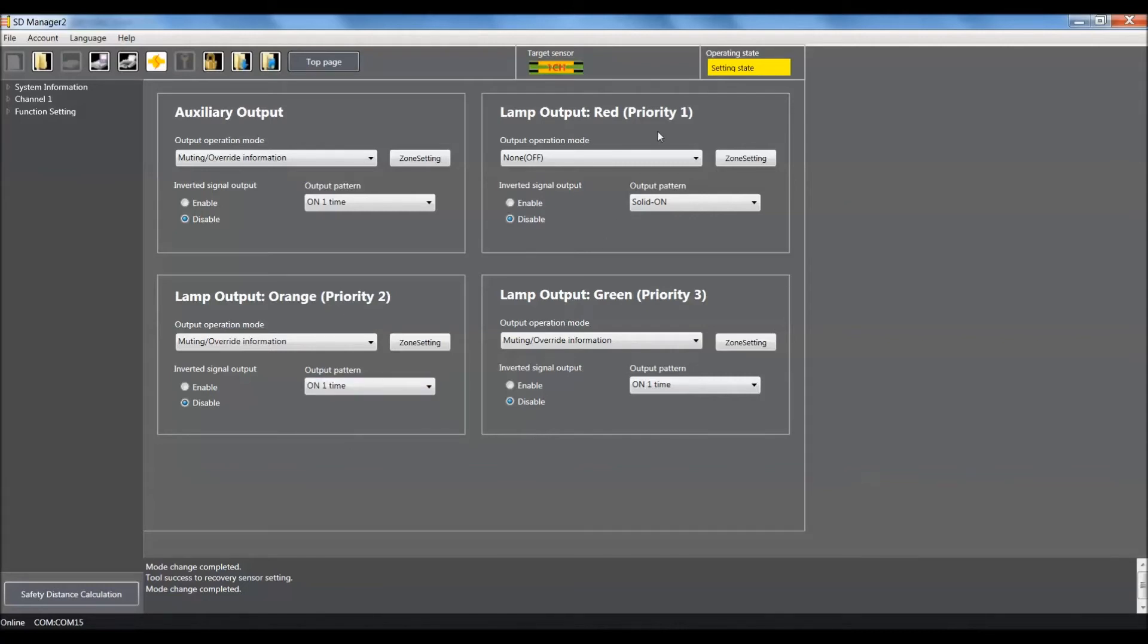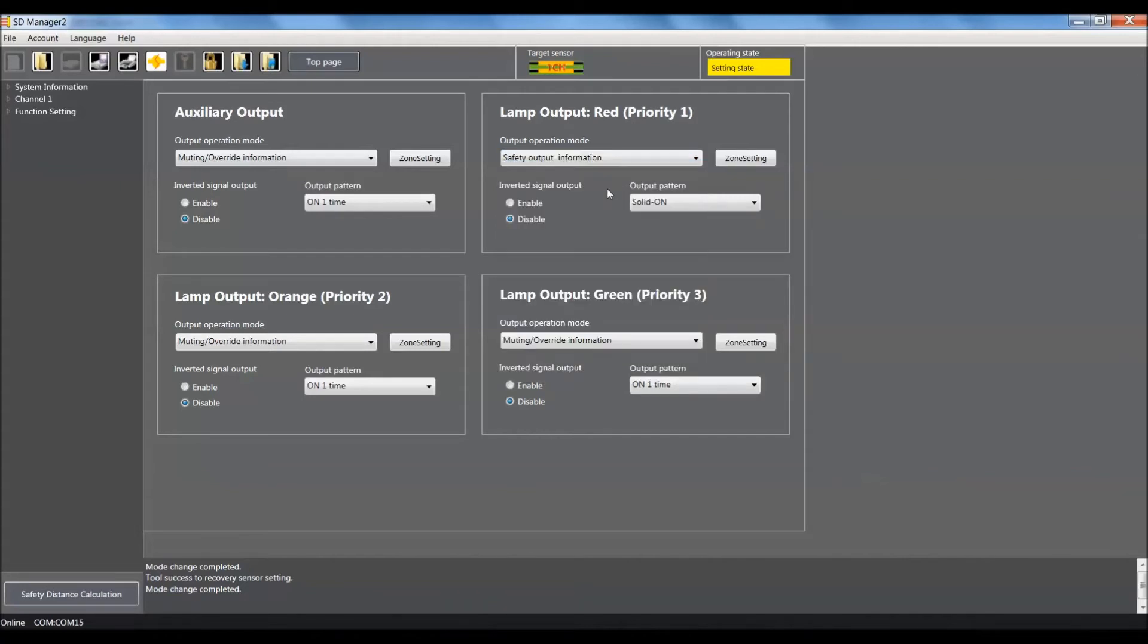For our priority one settings, we're going to set this up for safety output information, so we'll use the pull-down, scroll all the way up and it's the first selection available. We'll make sure that the inverted signal output is enabled and that we have it set for solid on.